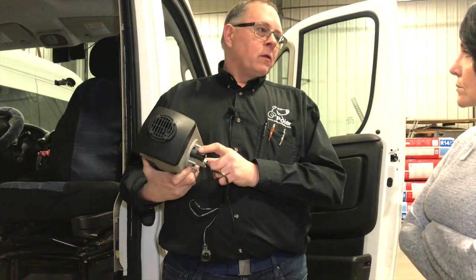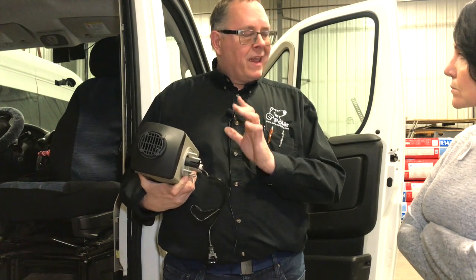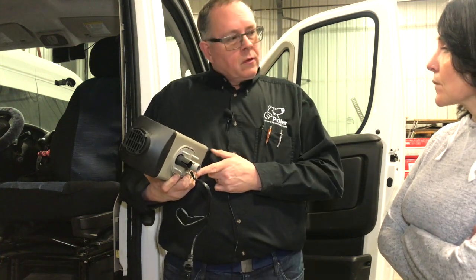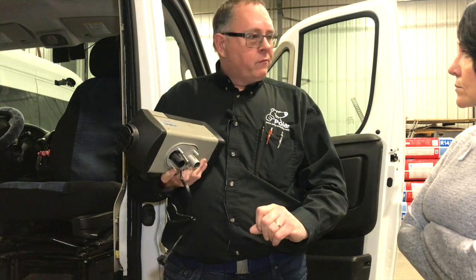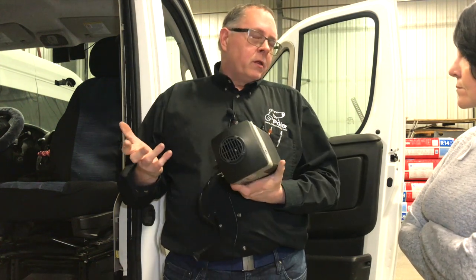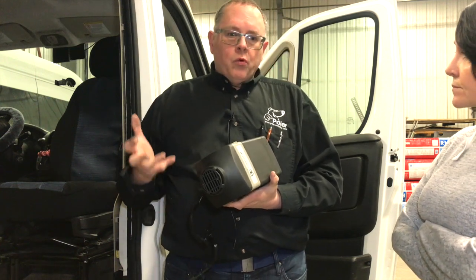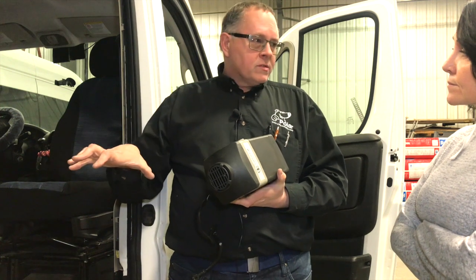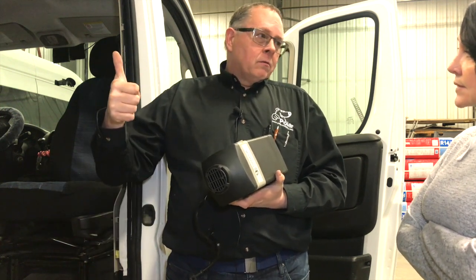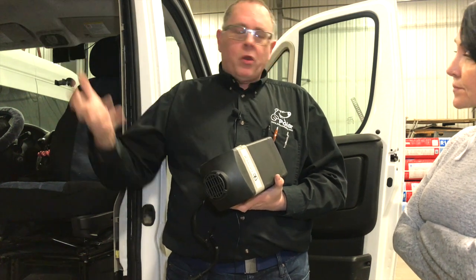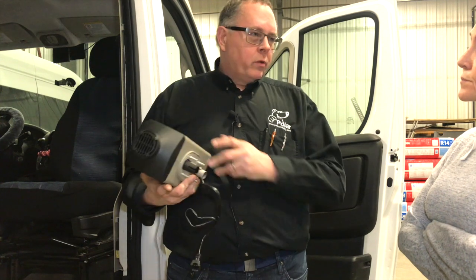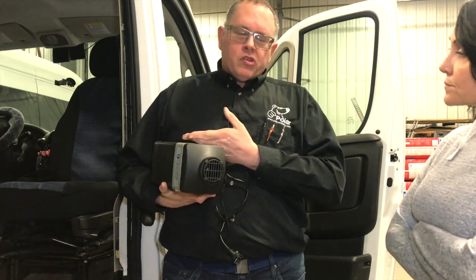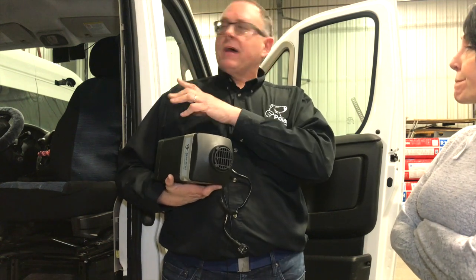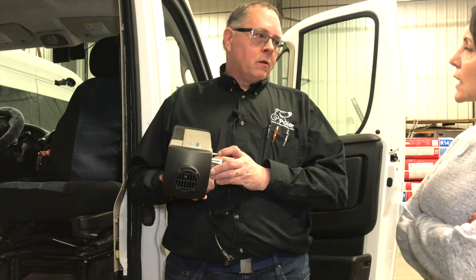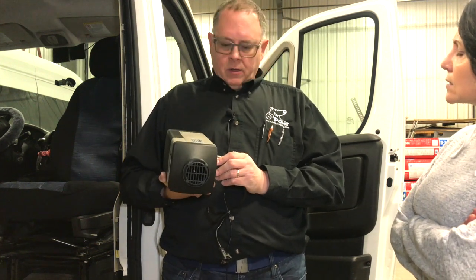We try to run the intake to a clean air area that isn't in the direct travel path of the vehicle when it's moving. Likewise with the exhaust, you don't want it to pool underneath the vehicle, especially for long periods when it's sitting, because the fumes could get sucked back up through an open door or holes in the floor. Anyone using a fuel-fired heater should always have a carbon monoxide detector inside the vehicle. You don't want it sucking its own exhaust in at all, so keep the two pipes as far away from each other as possible.